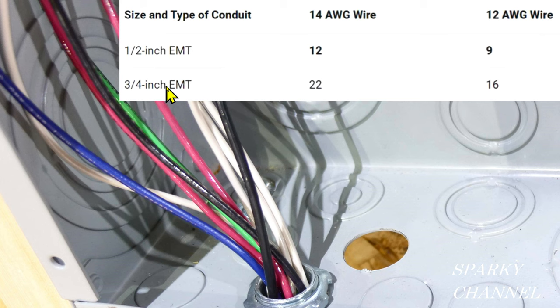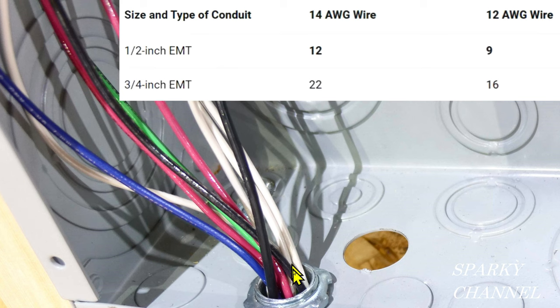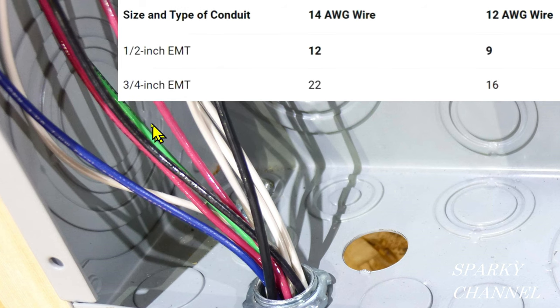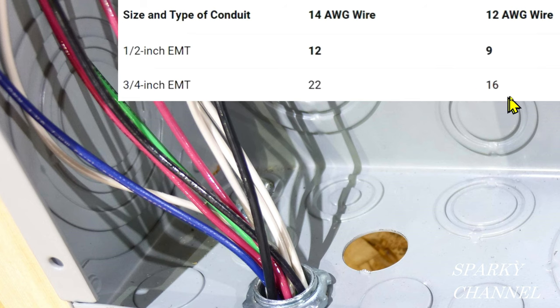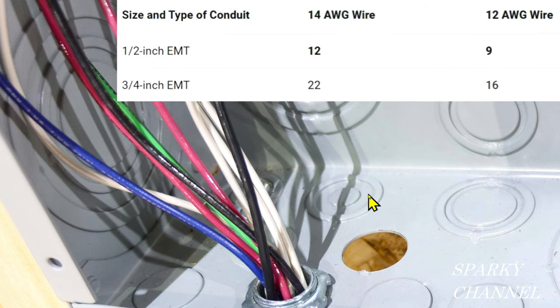I'd like to say though, it's not good practice to put this many wires in a half-inch conduit. I would recommend going to three-quarter-inch EMT, where you can actually put 16 12-gauge wires.